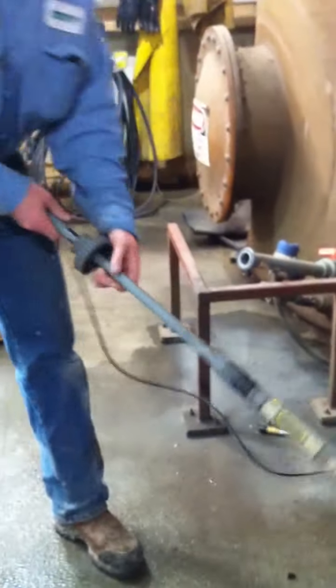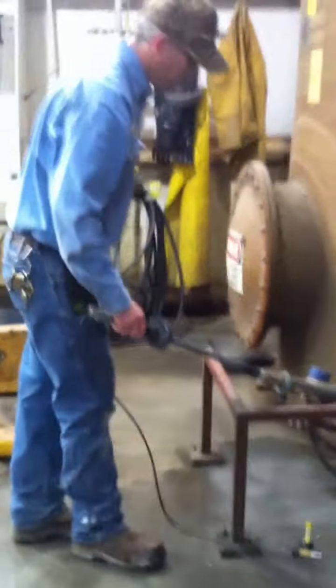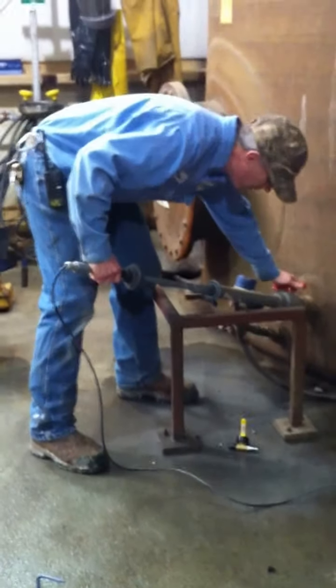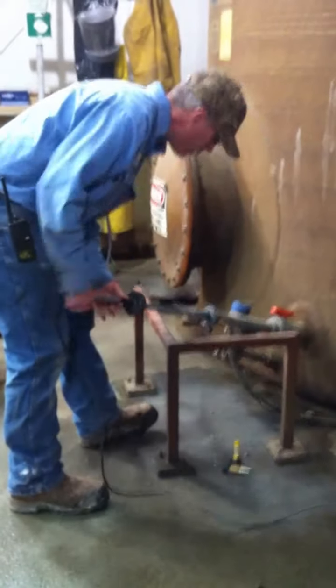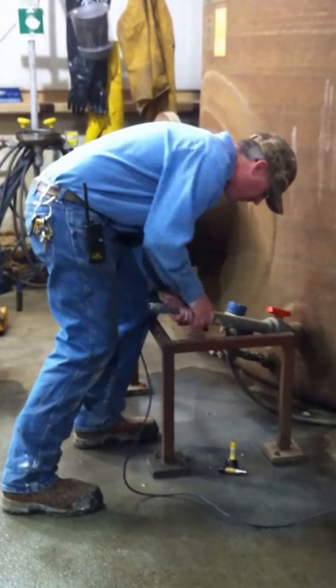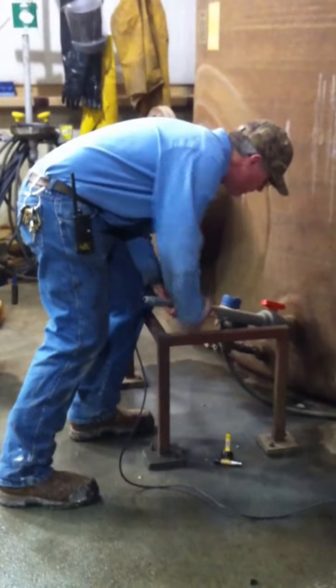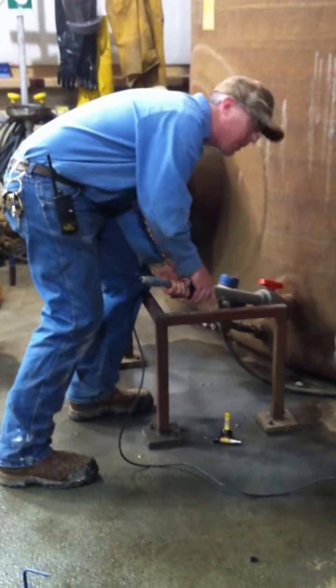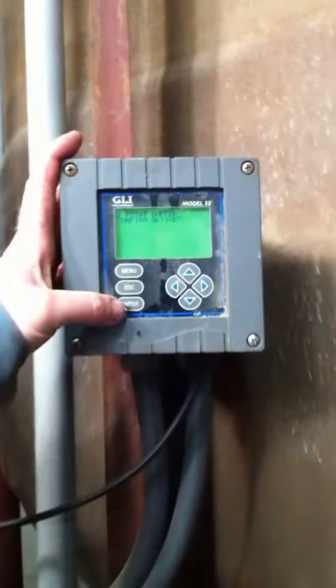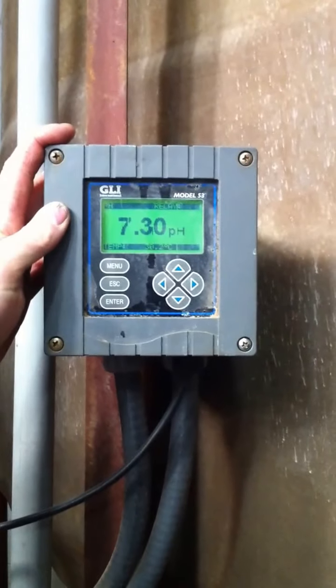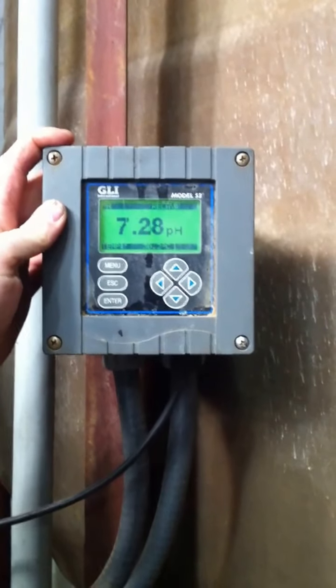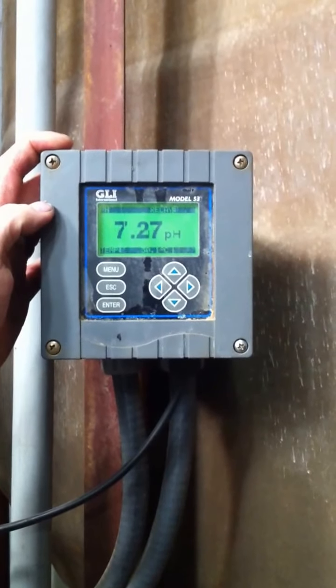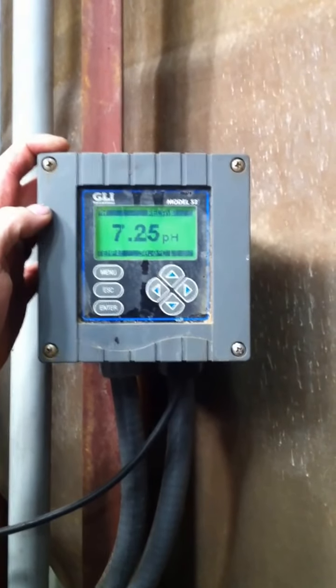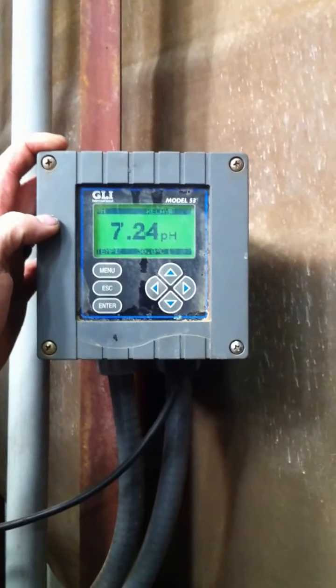And then I'm going to reinsert it to the process. Open my valve. Reseat the probe. Tighten the union. And then I'll go back to the controller. At that point, I'll go ahead and activate the probe. And it's reading our process right now at a 7.272625. It'll stabilize here in just a few seconds.